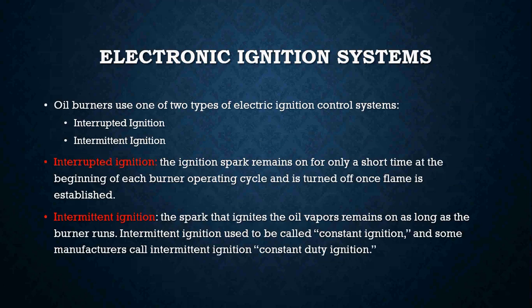Burners use two types of ignition control systems: interrupted ignition and intermittent ignition. Interrupted ignition has the spark on only for a short period of time at the beginning of each burner operating cycle, and then it turns off once the flame is established. With intermittent ignition, on the other hand, the spark stays on as long as the burner is running. Intermittent ignition used to be called constant ignition, and some manufacturers call it constant duty ignition, so don't get them confused.